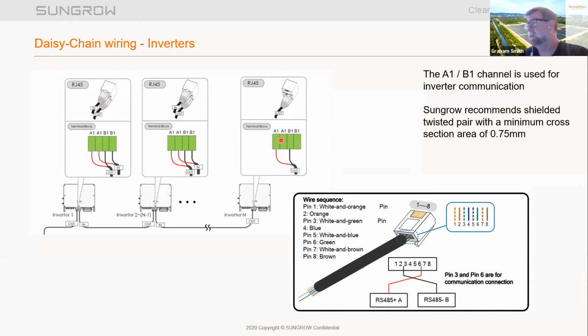So you come out of the A1B1 and you go to the next inverter and you come into A1B1, you come out of A1B1, go to the next inverter, etc., etc. In all of our inverters, there is a screw terminal block, or there's an RJ45. You can use RJ45 if you like, but I prefer to use the screw terminal, because if you're making these RJ45 plugs up on site, there's always a chance that there's a bad connection, and it'll cause you no end of trouble. So I generally prefer to use the screw terminals. We do recommend that you use shielded twisted pair with a minimum section area of 0.75.